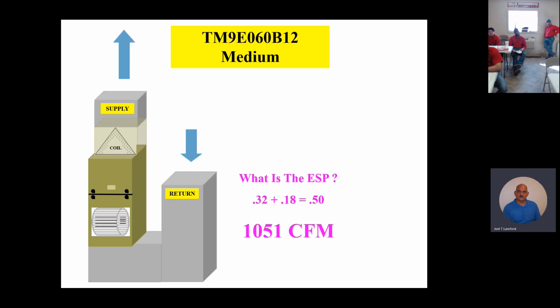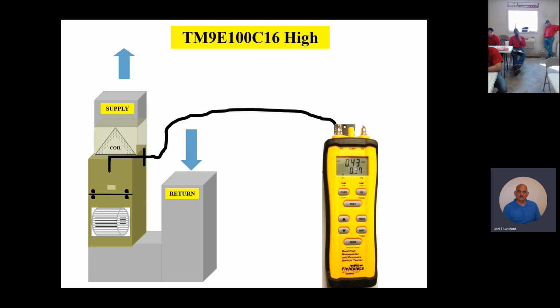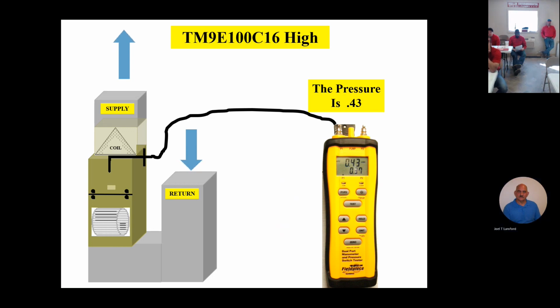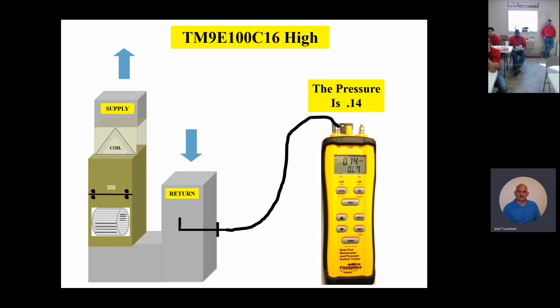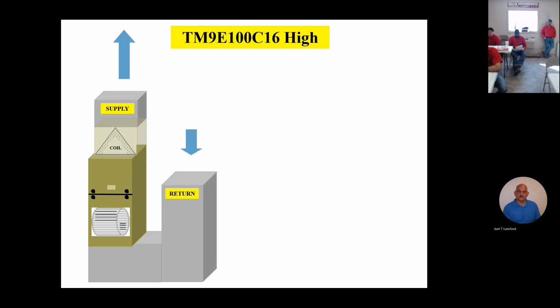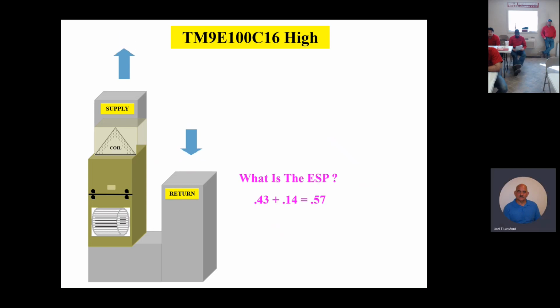All right, let's do a couple more just to make sure we've got this. Here we have a TM9E100C16 on high speed tap. Supply side static is 0.43. Return static is a 0.14. So 0.43 plus 0.14 equals what? 0.57. Okay, good, excellent. And now the reason I did this one here, guys, is because I want you guys to extrapolate a little bit. It kind of falls in between two values. And so it's not a 0.5, it's not a 0.6, it's a 0.57. So what would you call the CFM? You're kind of extrapolating off the chart.